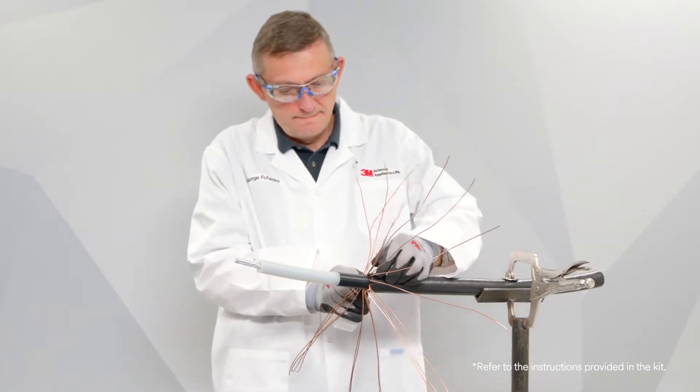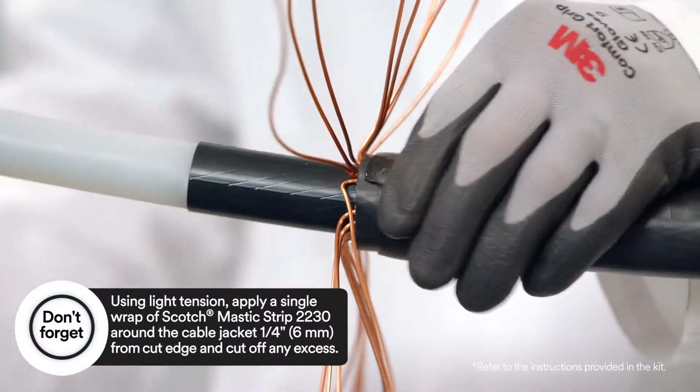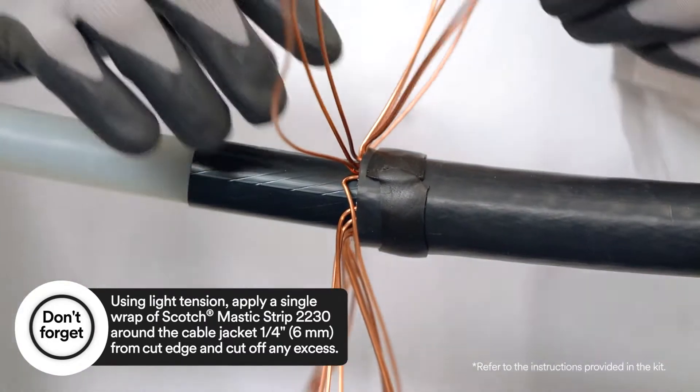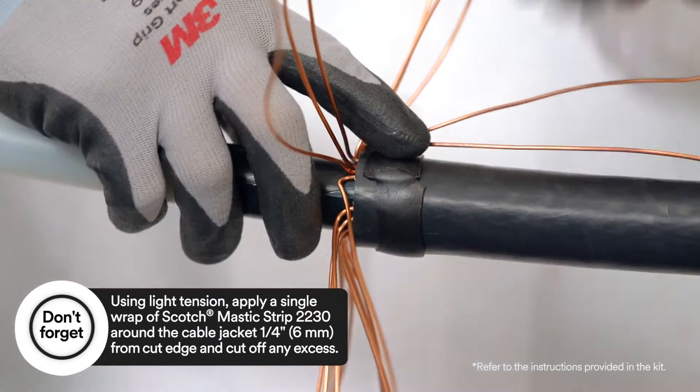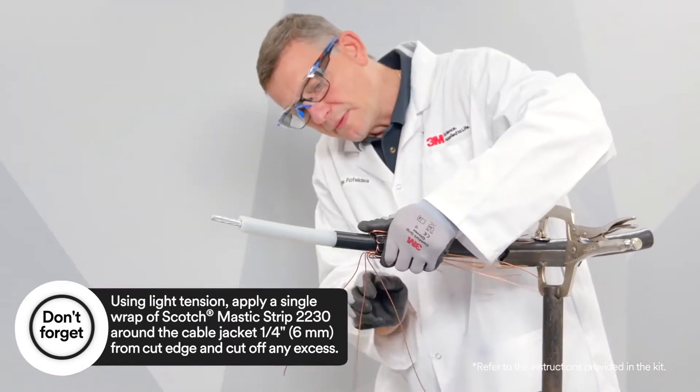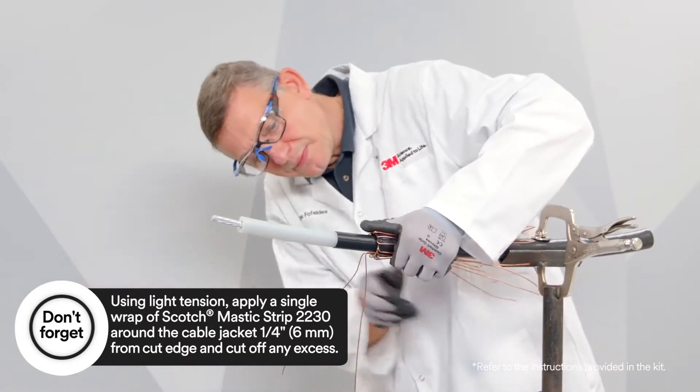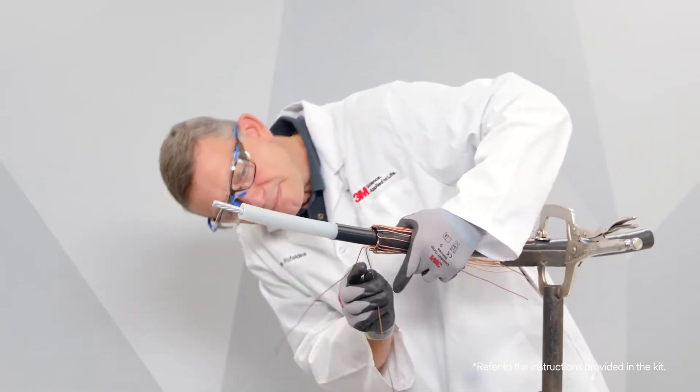After you've applied Scotch Mastic Strip 2230, bend the neutral wires back over the applied sealing mastic. Make sure all concentric neutral wires that are bent back are equally spaced and do not cross each other.